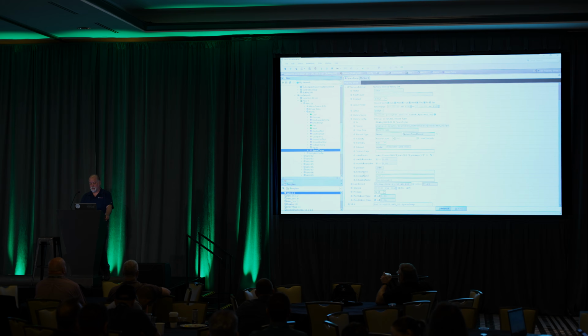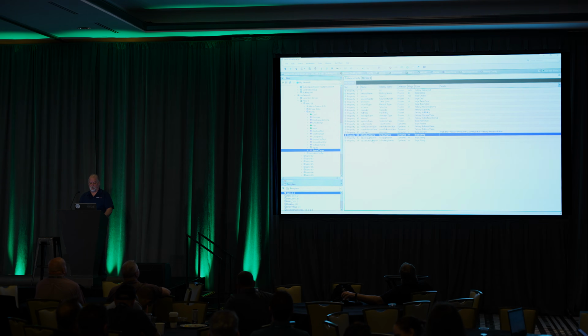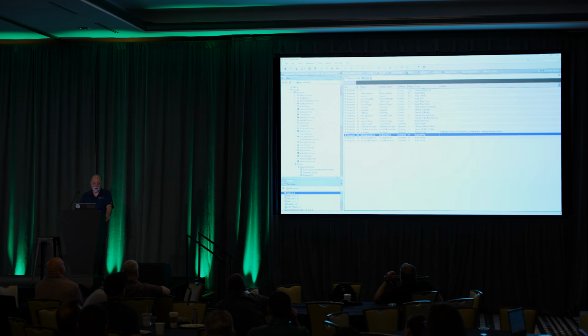In this case, I've added some actual N4 tags to these history config components. And I'll point out that really all this is, is a string slot that has the metadata slot flag set on it. So that's exactly the same thing that you do with the metadata browser, or that people did in AX building history groupings, okay? All you're doing is adding a string tag to it. And in this case, we have a namespace and a tag name, as opposed to it just being a string. But you can build your history groupings out using these tags.